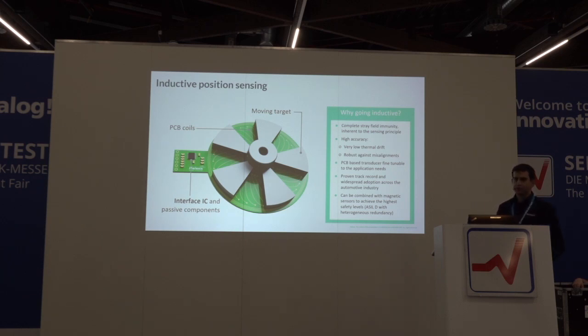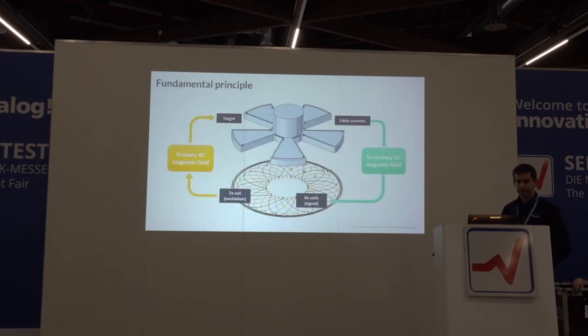So now that we know the big lines, let's see how the transducer itself works. We said we have a set of coils on the PCB, and there are two types. There's a first coil, the transmission coil, this round one, which generates an AC magnetic field—actively driven by an AC voltage. This primary AC field excites eddy currents in the conductive target.